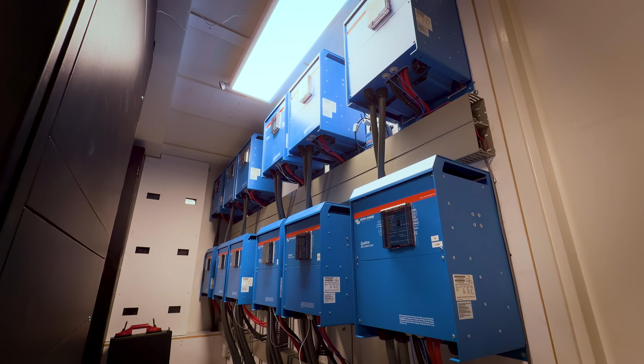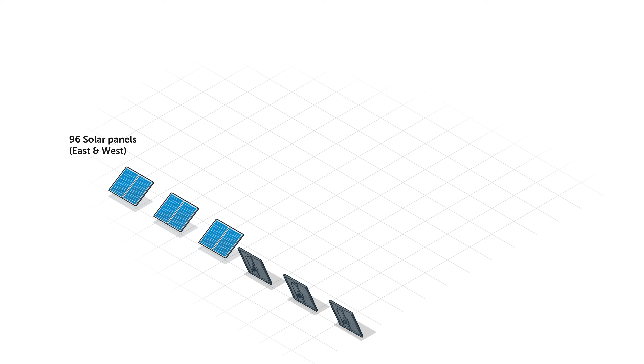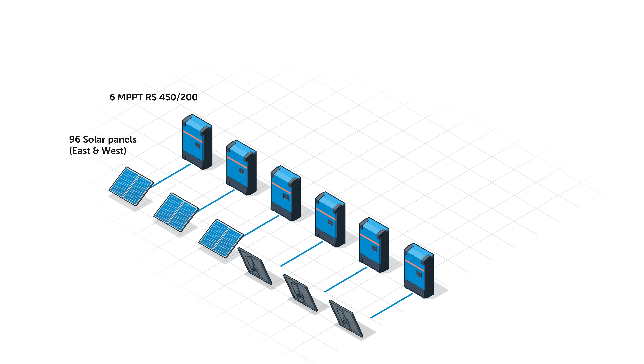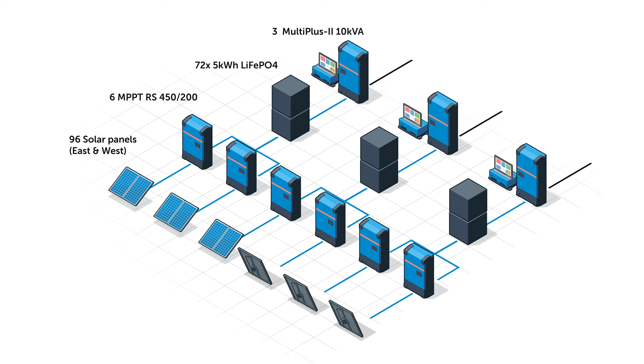Together, they've built something that neither of them had done before at this scale. There are two separate systems. 96 solar panels in a 50% east, 50% west configuration are out in the field. They feed 6 MPPT RS 450-200 solar charge controllers, 3 10 kVA MultiPlus 2 units, and 72 5 kWh LiFePO4 lithium batteries. These are treated as 3 different systems with their own Cerbo GXs and screens.